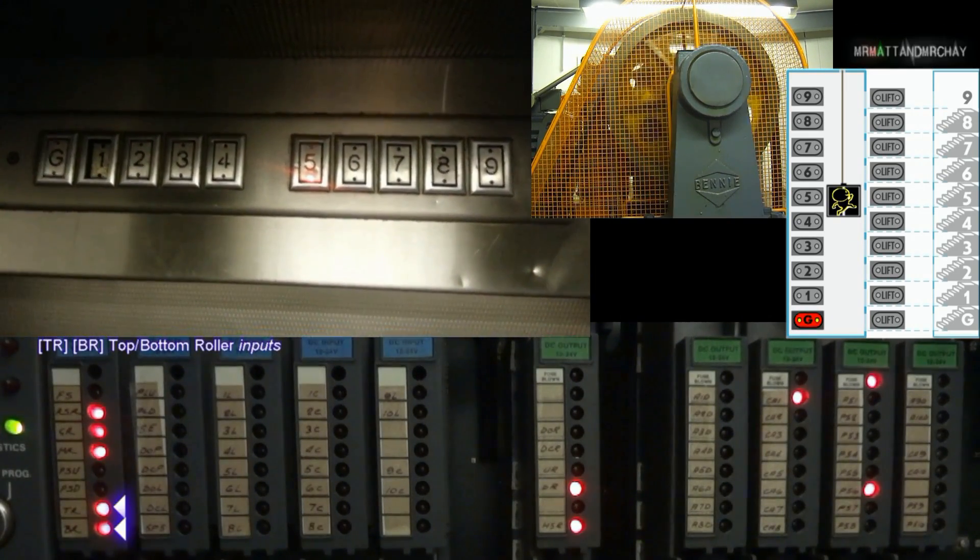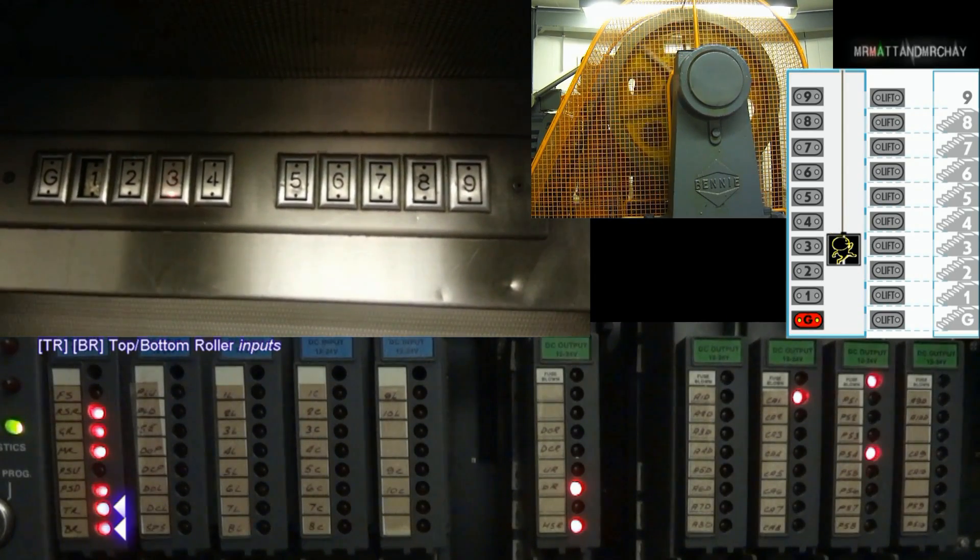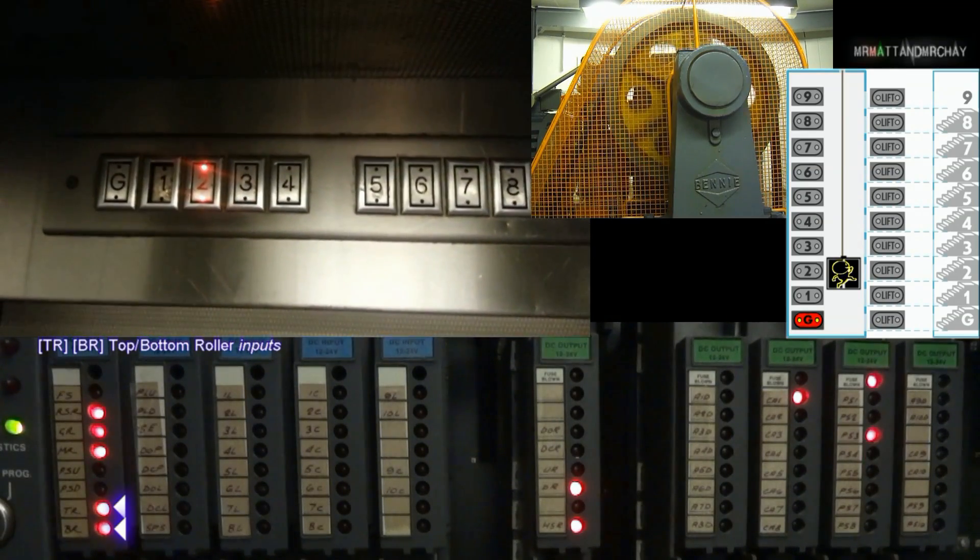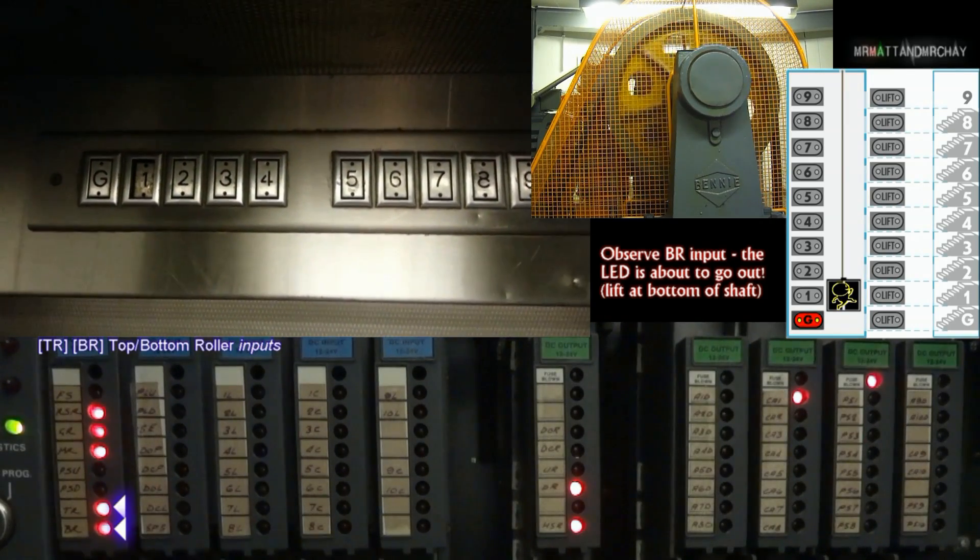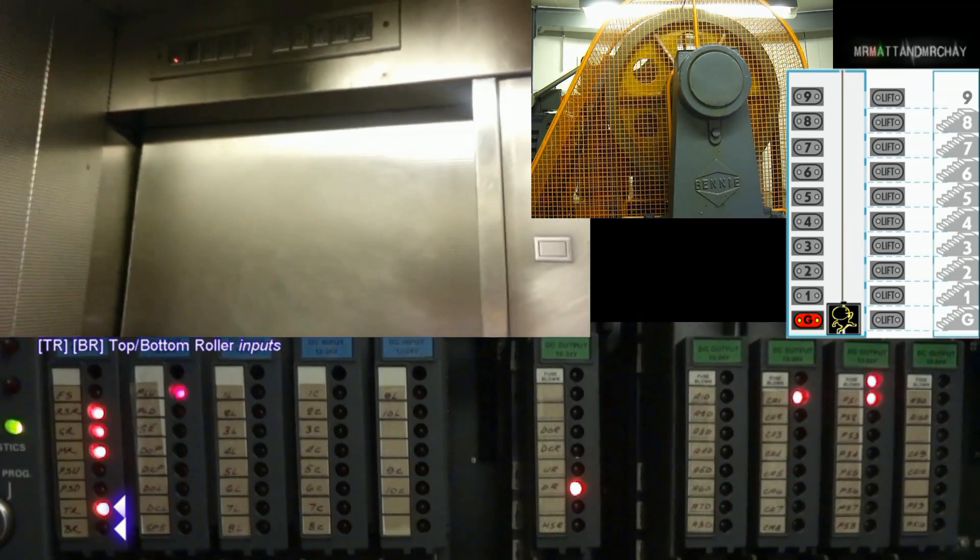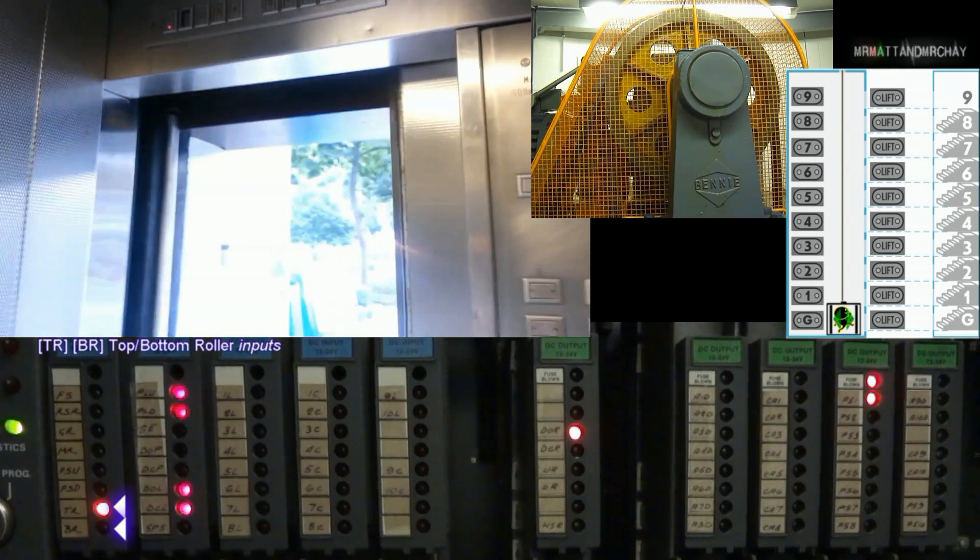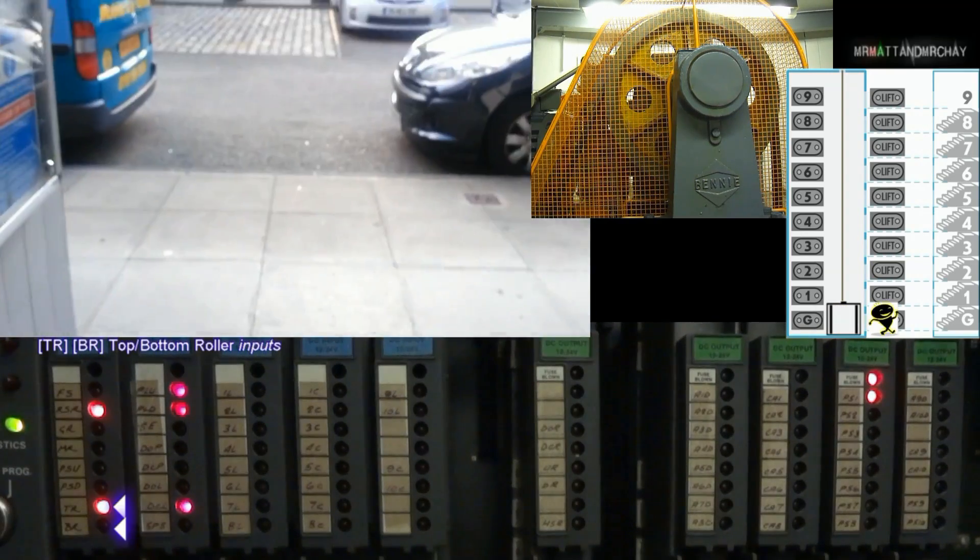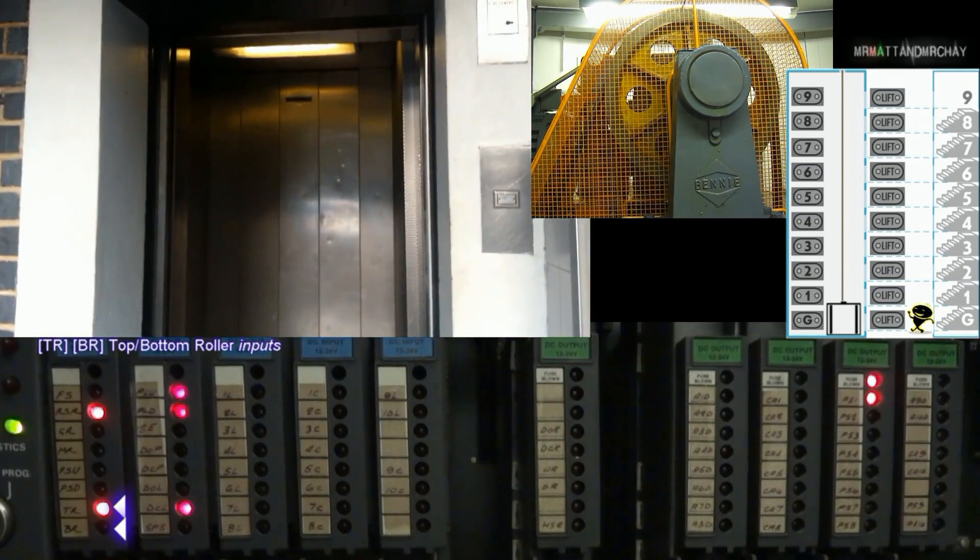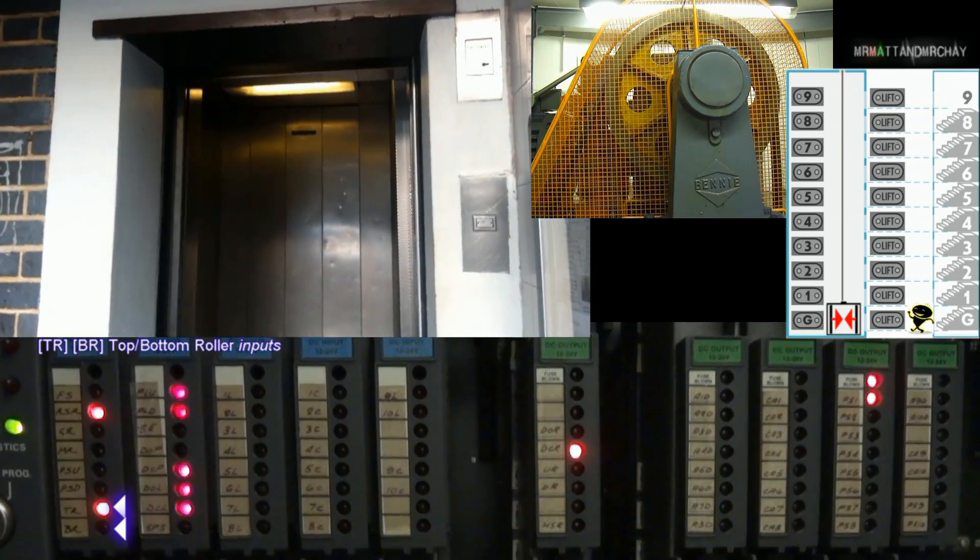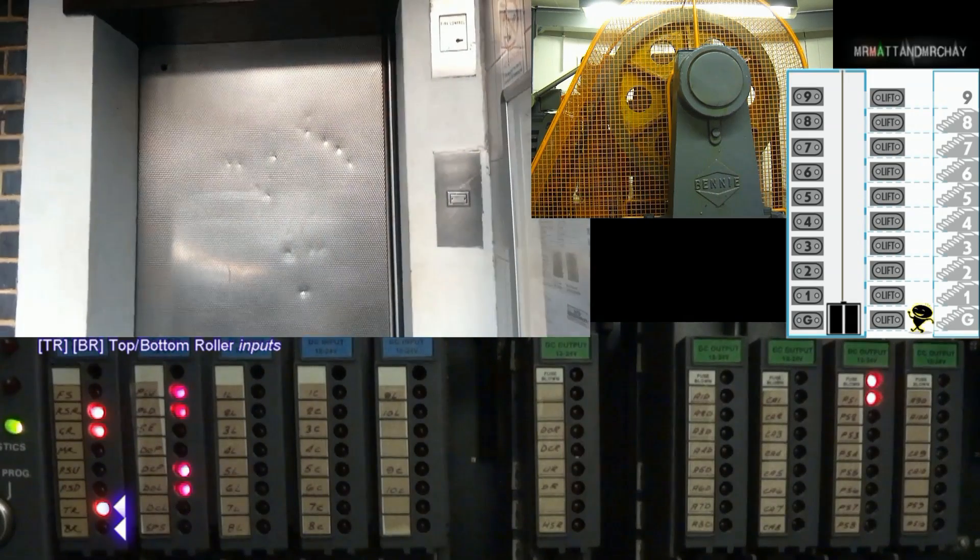TR, top roller. There is a roller switch at the top and bottom of the shaft. When the lift is at its highest floor, TR is activated. It's the same for BR, as this is the bottom roller switch at the bottom of the shaft. If the controller were to forget the position of the lift car, it can then run the lift down at a slow speed blindly until the lift reaches the bottom of the shaft, where BR would activate. The lift position is then reset to the ground floor. These switches are possibly also a backup for a slow down input for a car approaching the end of the shaft, in case it hasn't slowed down already.